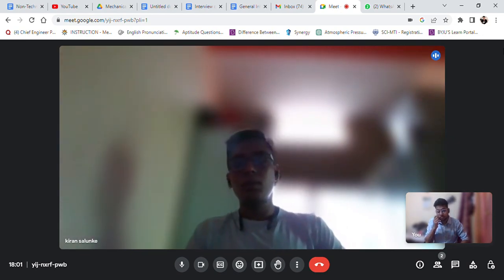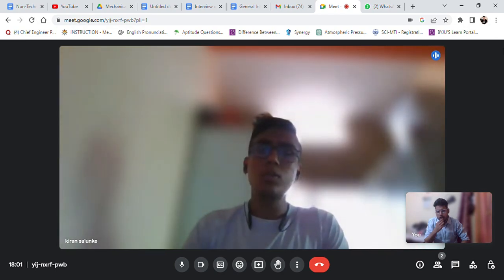Talking about the physical method, the priming funnel is situated on the casing of the centrifugal pump. In this case, we pour water from the priming funnel and fill the entire casing and the suction side of the centrifugal pump. The water takes the place of the air, and the air is expelled from the priming funnel.